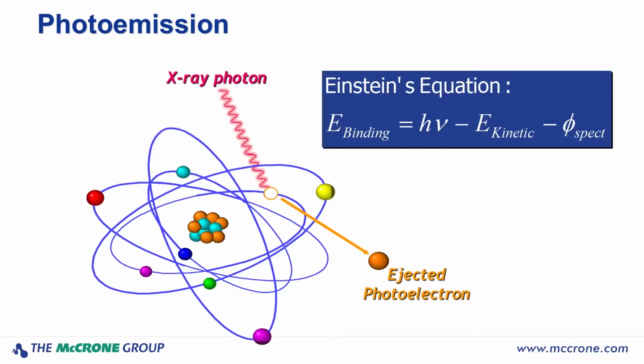So if we look in detail at the photoemission process, what's occurring in our material is that the X-rays from their source can ionize atoms in our material and produce photoelectrons. And the photoelectrons' energy is then the energy that binds them in these filled orbitals around the nucleus of an atom. And the energy of the photoelectrons is expressed as binding energy, and that's calculated from the energy of the photons. So for aluminum K-alpha X-rays, that's 1486 eV.